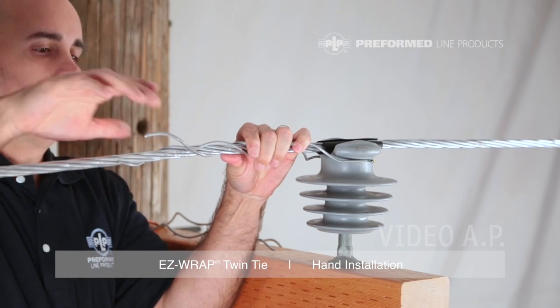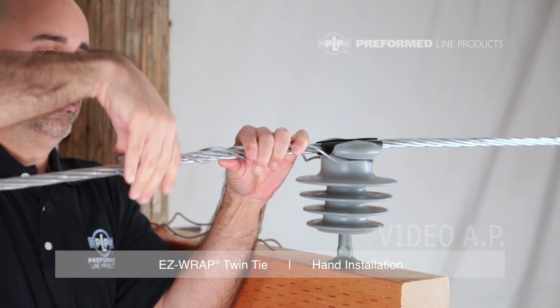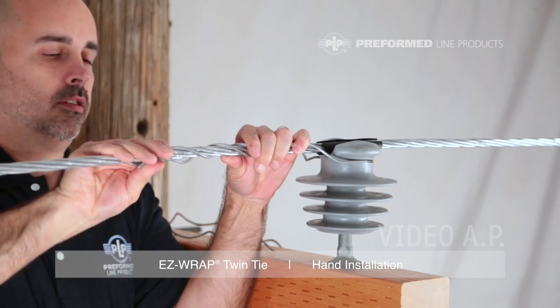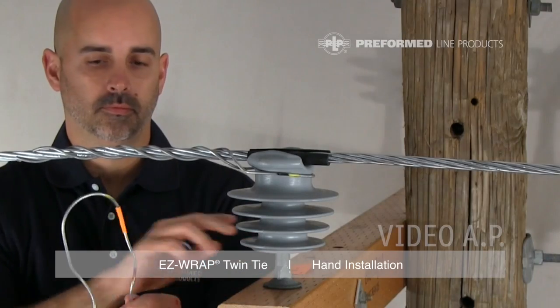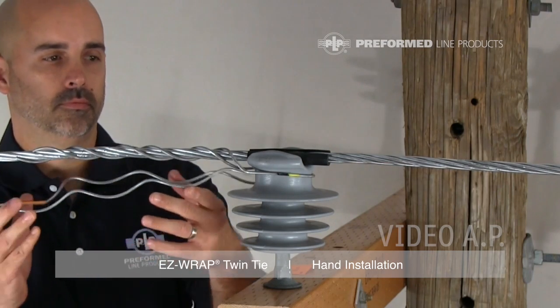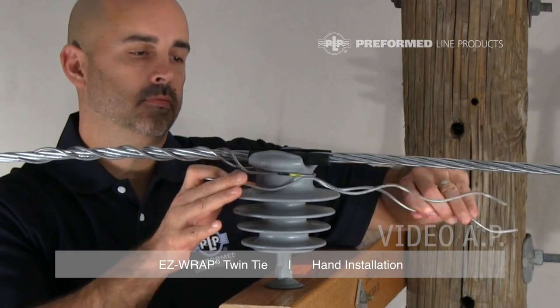Wrap the second leg starting from beneath the conductor. Make sure the tie loop is tight on the neck of the insulator and wrap this leg to completion. Install the second half of the EZ-WRAP Twin Tie following the previous steps.